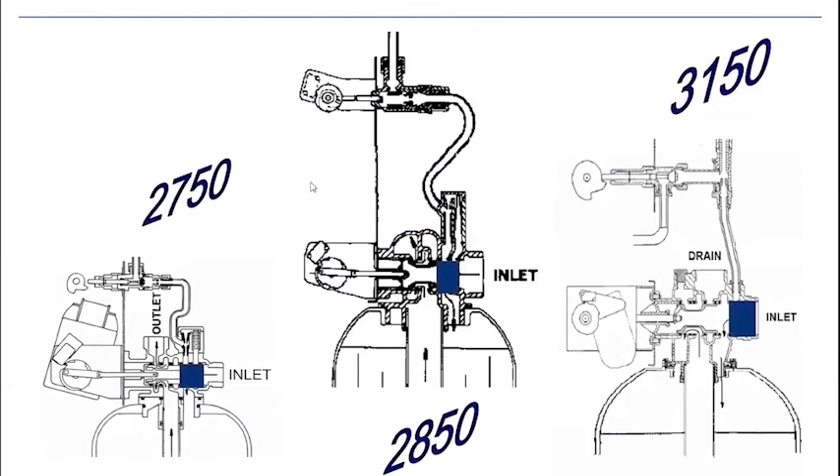There's where the water comes in — the inlet down into each valve. Exact same flow path in both. Here's where you have the backwash portion of the valve and then the outlet portion of the valve. It's blocked off, and this slides back and forth, diverting the flow through different channels, directing the flow in different directions through the valve in order to backwash the filter, generate a brine draw, rinse the filter or softener, and then fill that brine tank in the final cycle of the system.